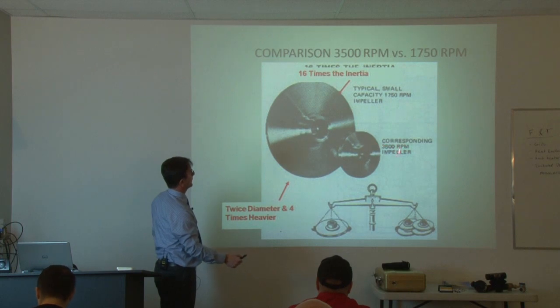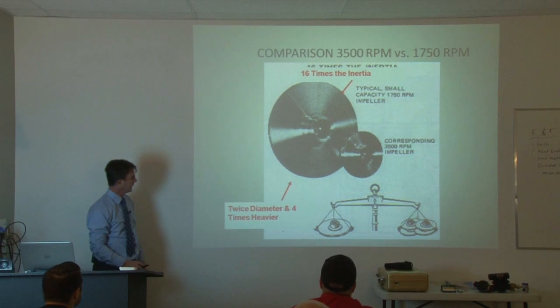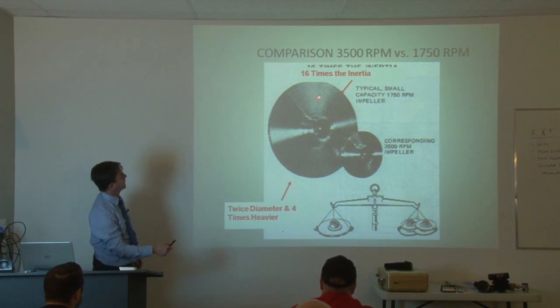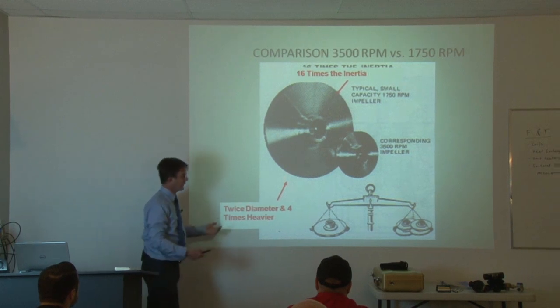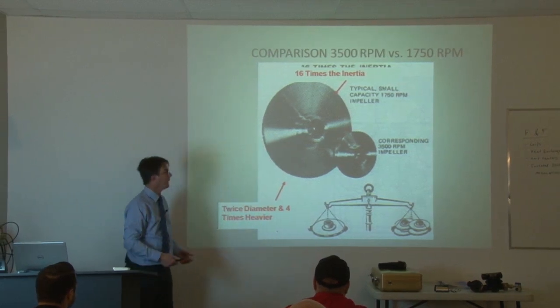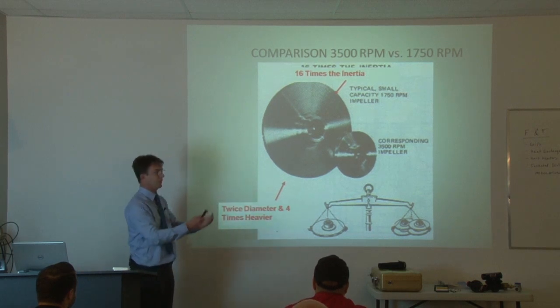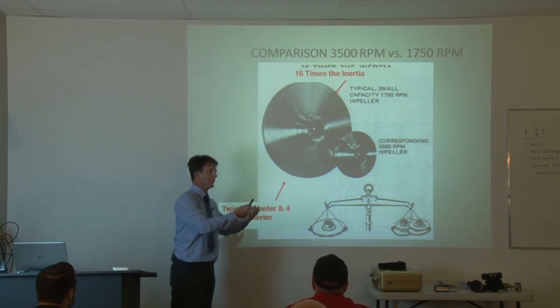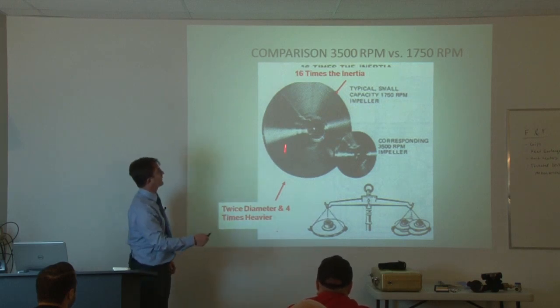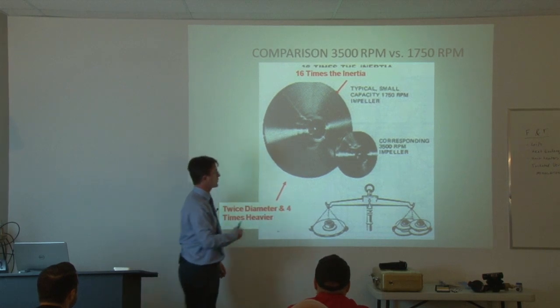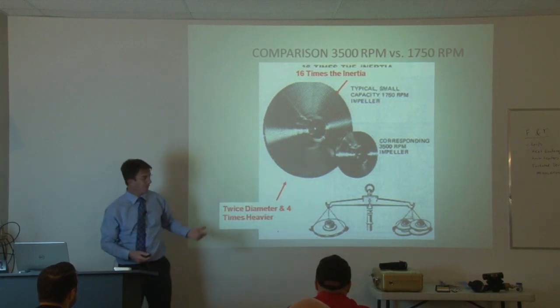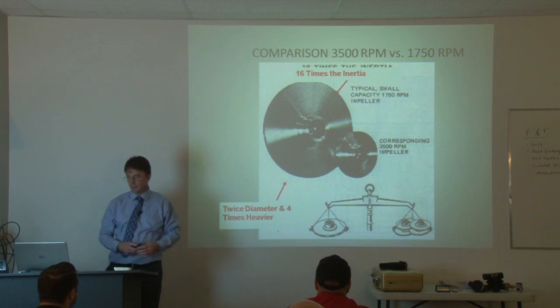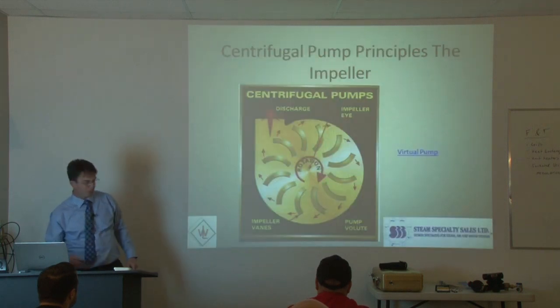Shipco only uses 3,500 RPM impellers. A 1,750 RPM impeller is twice the diameter and four times heavier, so it takes more power to run it. Because condensate pumps are on and off, there's a lot of surge power needed to get the pump rolling. With a 1,750 RPM impeller, there's that much more power required to start it, and because they're bigger, they're also much more expensive to replace.